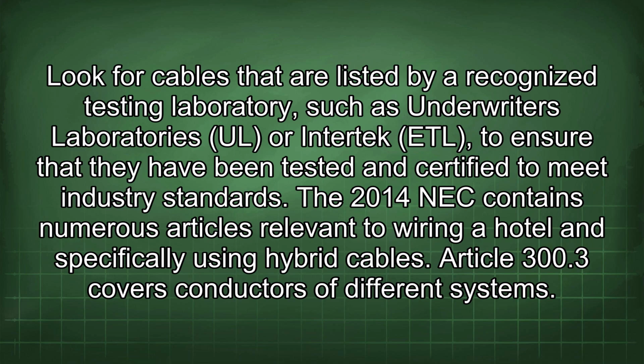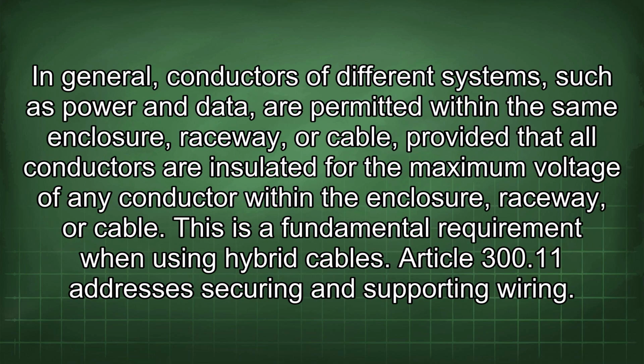Article 300.3 covers conductors of different systems. In general, conductors of different systems, such as power and data, are permitted within the same enclosure, raceway, or cable, provided that all conductors are insulated for the maximum voltage of any conductor within the enclosure, raceway, or cable. This is a fundamental requirement when using hybrid cables. Article 300.11 addresses securing and supporting wiring.